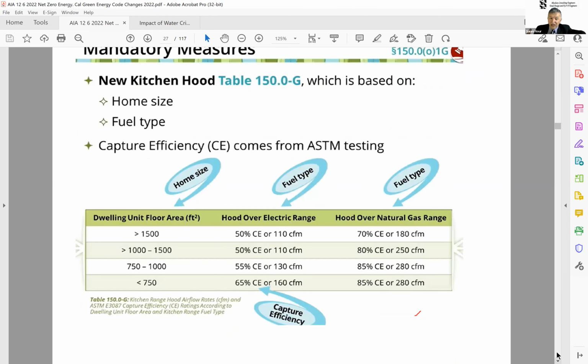You can have different floor areas. Your electric range hood has to be 110 CFM or capture efficiency of 50%. Or if it's gas, it has to be 180 CFM, 70%. So it depends on the square footage, etc.